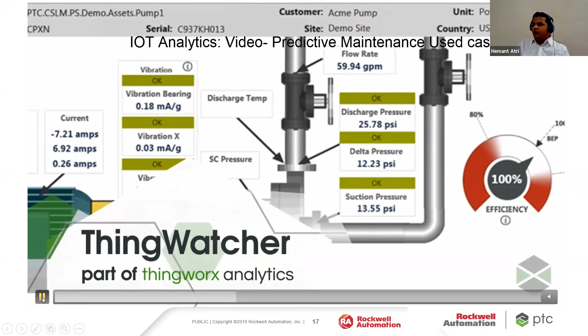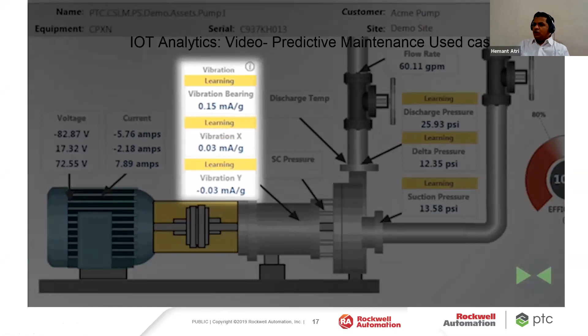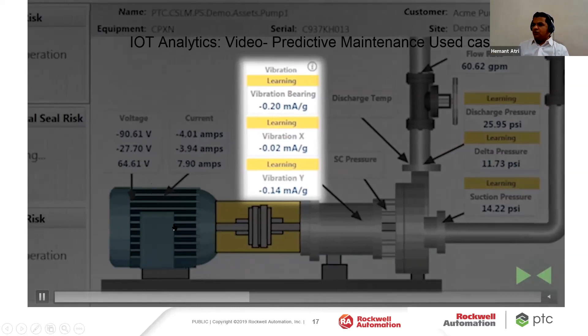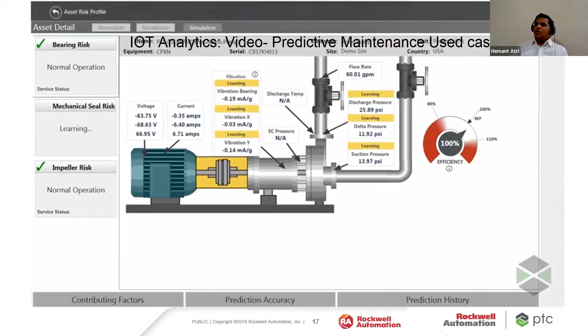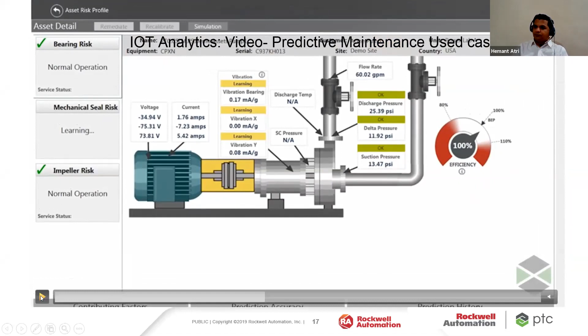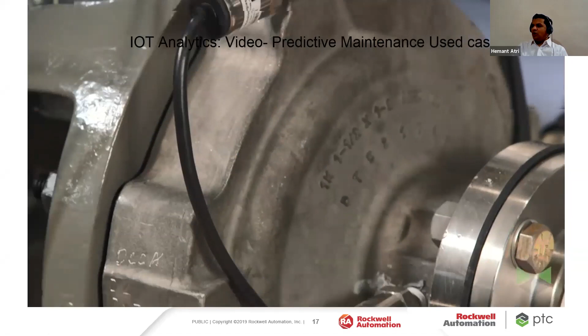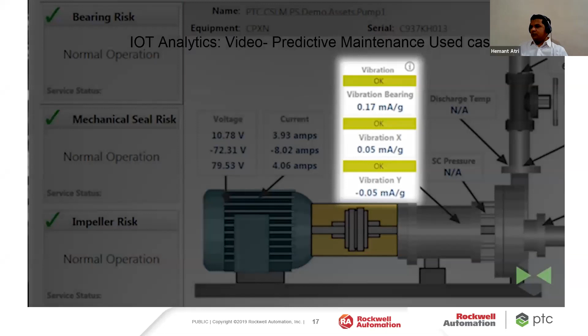What we are going to do here is create a blockage at the output of the pump, just to show what kind of changes will happen to the parameters that get affected, which in turn affect the performance or efficiency of the pump. You can see the current scenario being shown here. Bearing is normal, mechanical seal normal, impeller is doing its normal function. The efficiency, if you look, is at the maximum. So we will create a small diversion at the output of the pump, and then we'll see how the parameters get affected and how the model starts giving alerts.